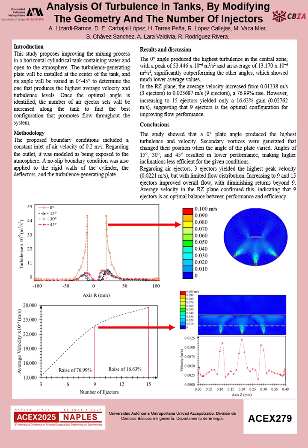Figure 2 indicates that increasing injectors from 3 to 9 raised the average velocity by 77%, from 0.013 meters per second to 0.0237 meters per second. Adding up to 15 injectors provided only an additional 17% gain, highlighting diminishing returns. The velocity field with 9 injectors exhibits homogeneous flow across the entire section.